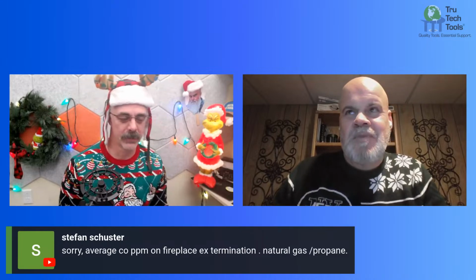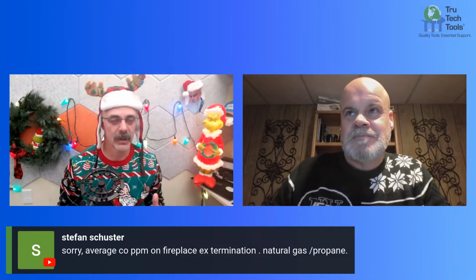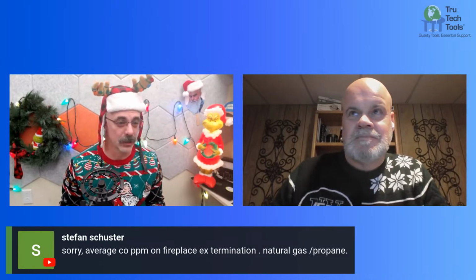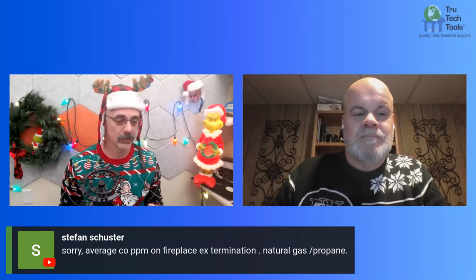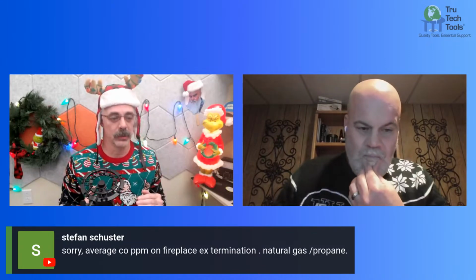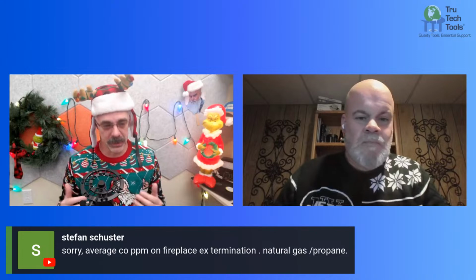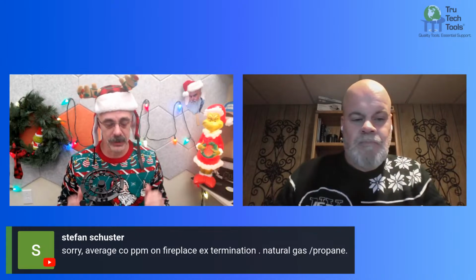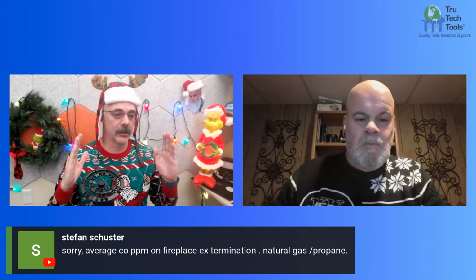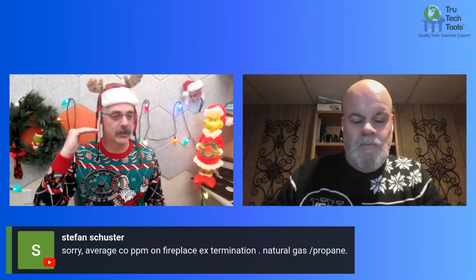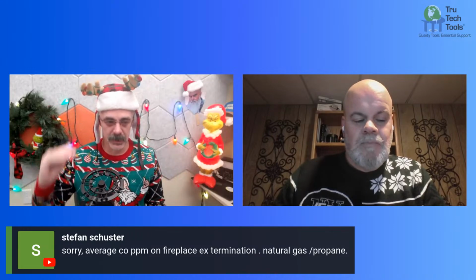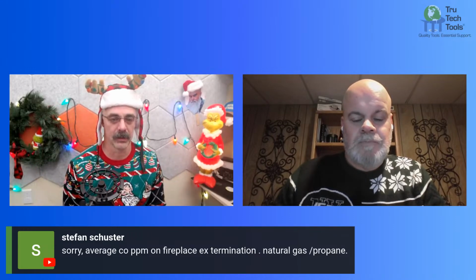Oh, I'm going to take this one here. Stefan, so average is a thing. You want it as low as possible. So get it as low as possible. And then look up BPI 1200, look at that specification. There's a table in there that lists all of the CO air free, and that's your high limit. But keep the CO as low as possible in there.